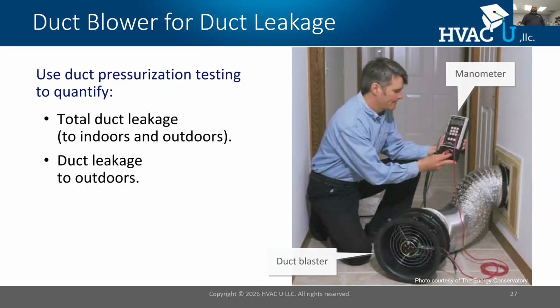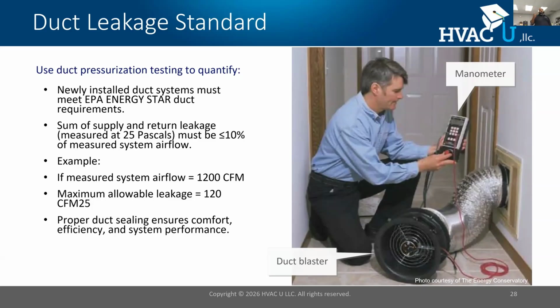All right, duct leakage to outdoors is another problem that we have to deal with because it's a bigger energy penalty. When we do total duct leakage tests, all right, we're going to either pressurize or depressurize the duct system using a duct leakage tester. And the test pressure reference here is 25 pascals.